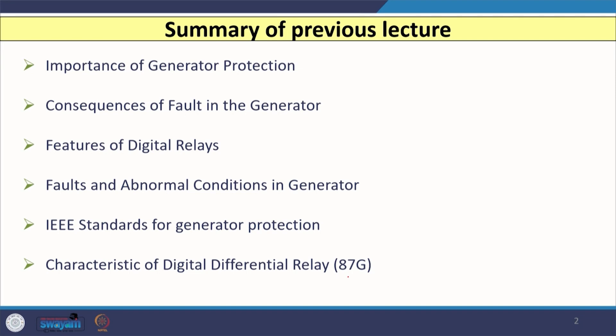We discussed three IEEE standards used by most utilities when designing a protection scheme for a large synchronous generator. We then started our discussion on the differential relay, discussing the two-slope characteristic of the digital differential relay — the 87G unit — and the significance of pickup, slope 1, and slope 2. The differential characteristic is plotted based on restraining current and operating current.